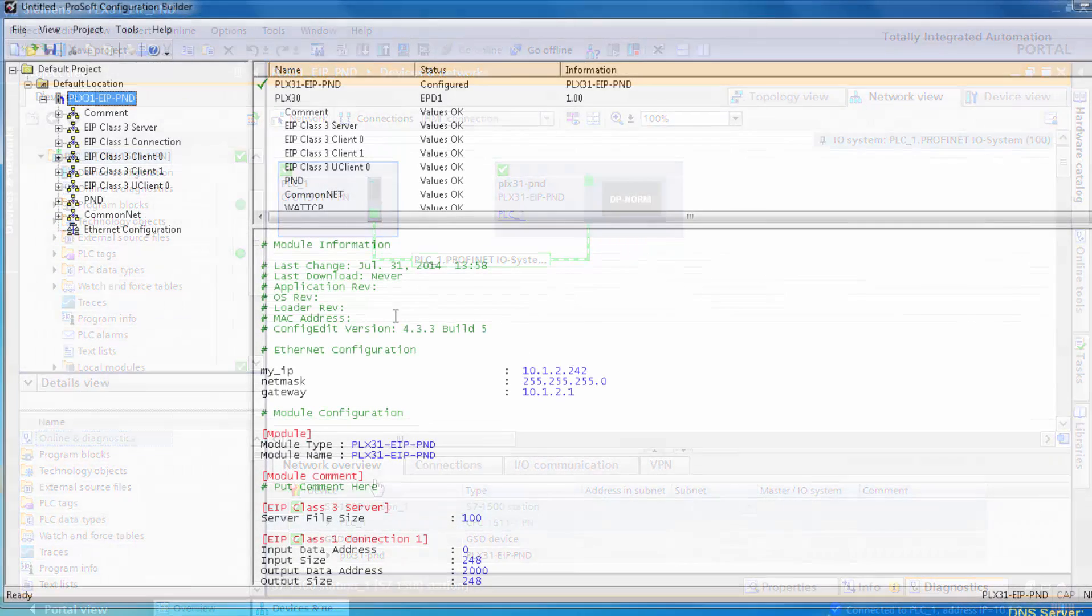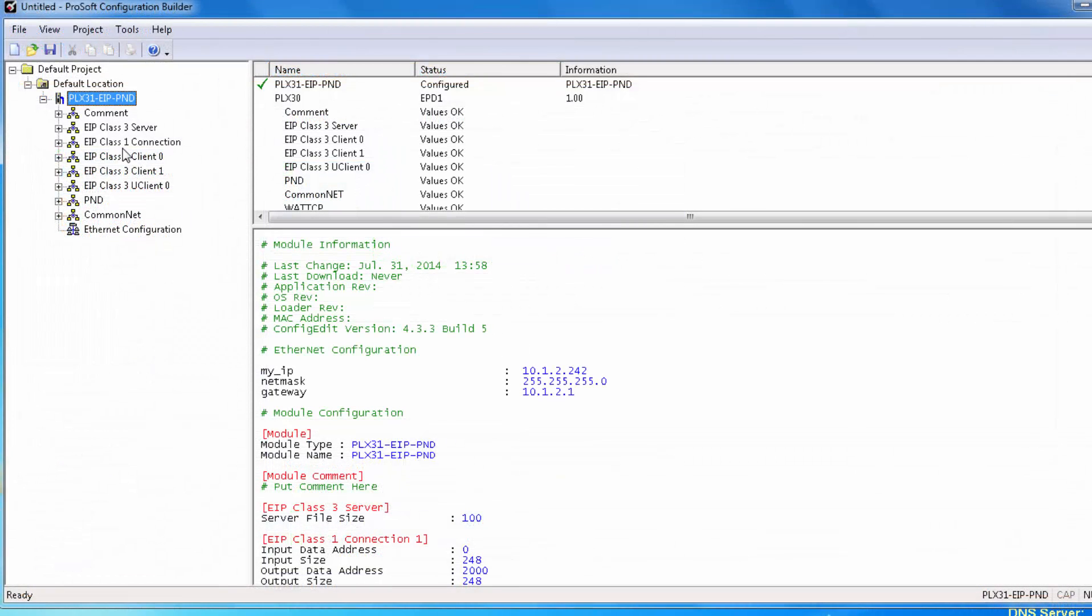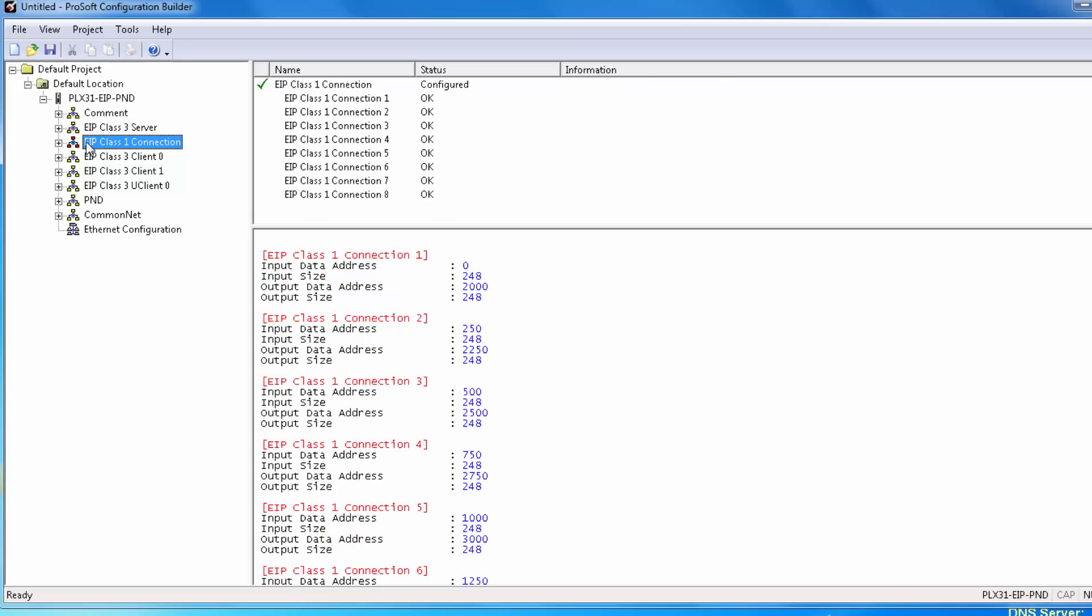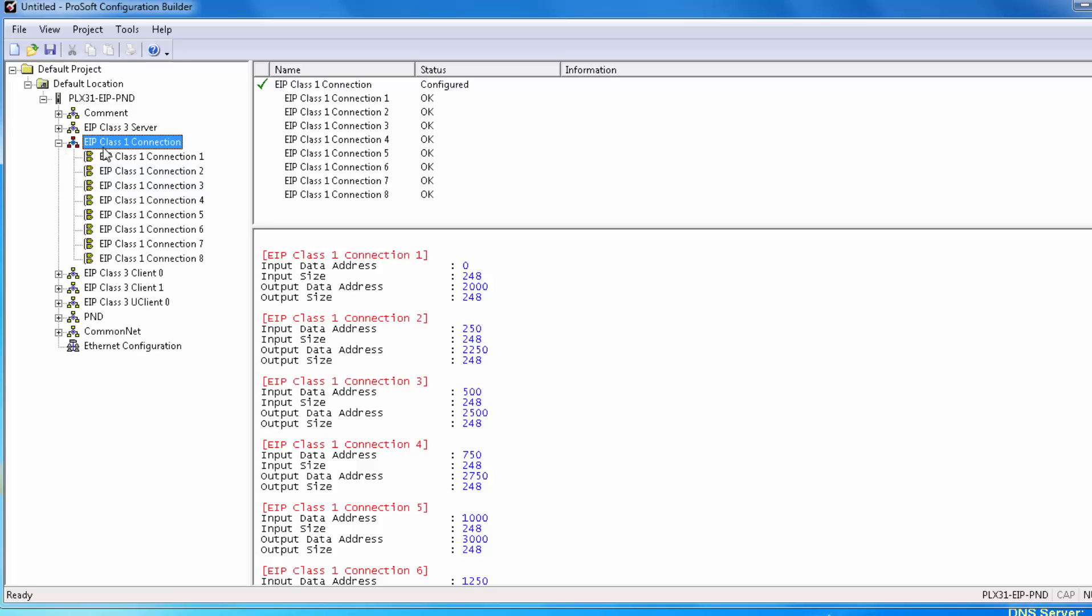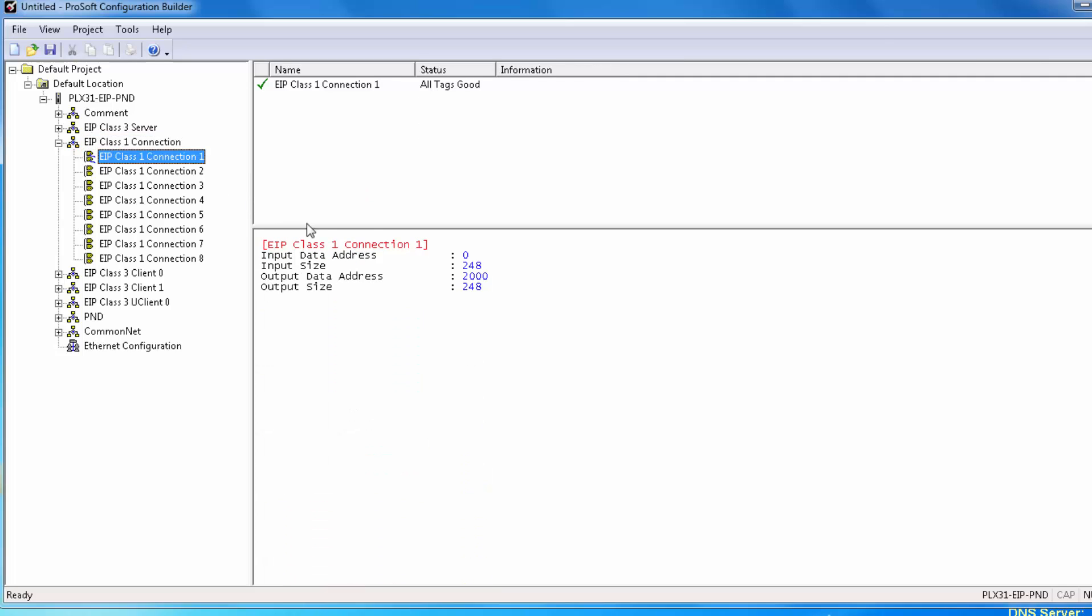Now we'll jump back to PCB to configure the connection parameters for our gateway to the Rockwell processor, so that the processor will see us as connected I.O. Expand EIP class 1 connection under the PLX31 EIP PND and let's take a look at connection 1. You'll notice that the default is 248 words per input and output and the starting point is word 0 and 2000 of our database.